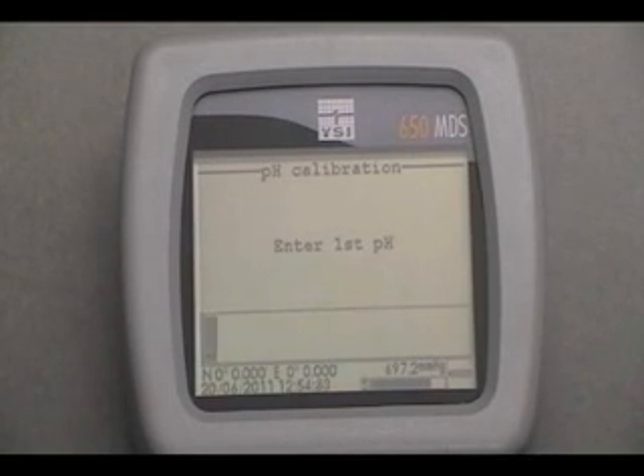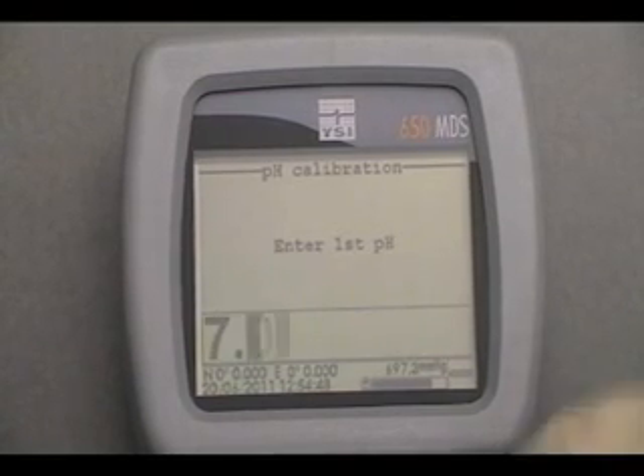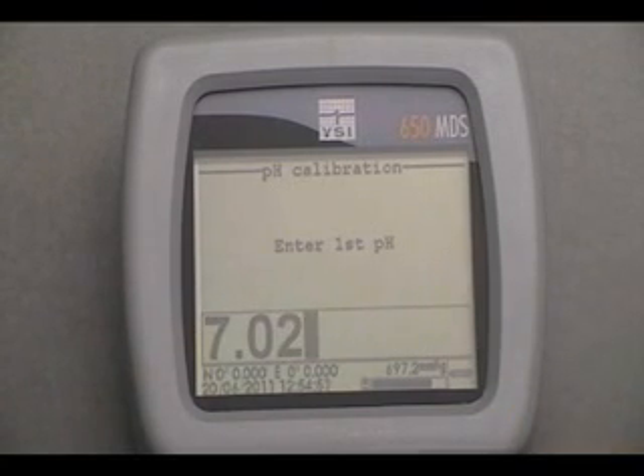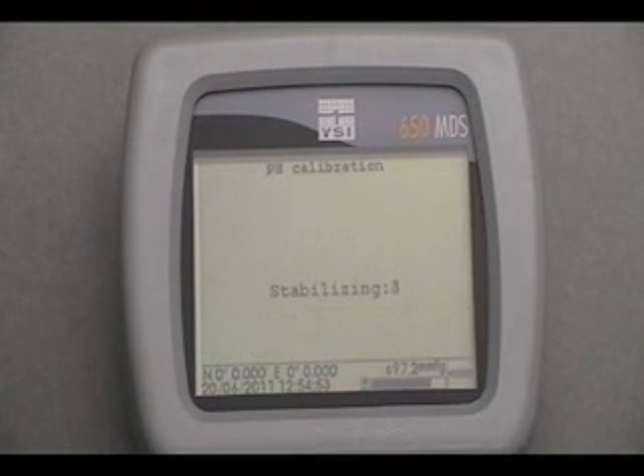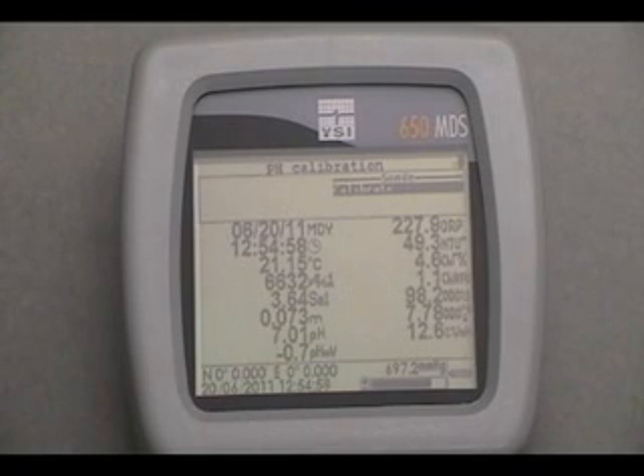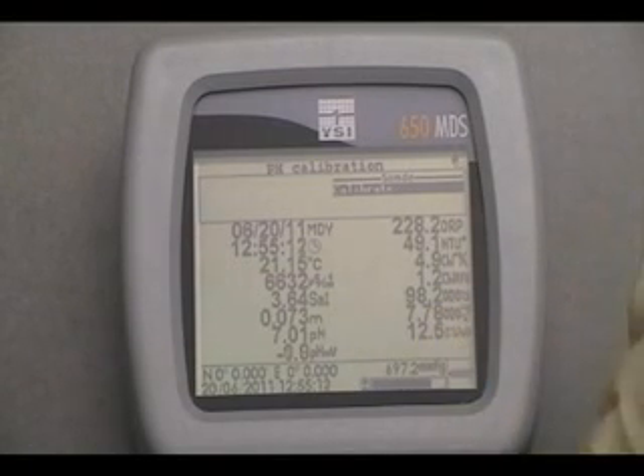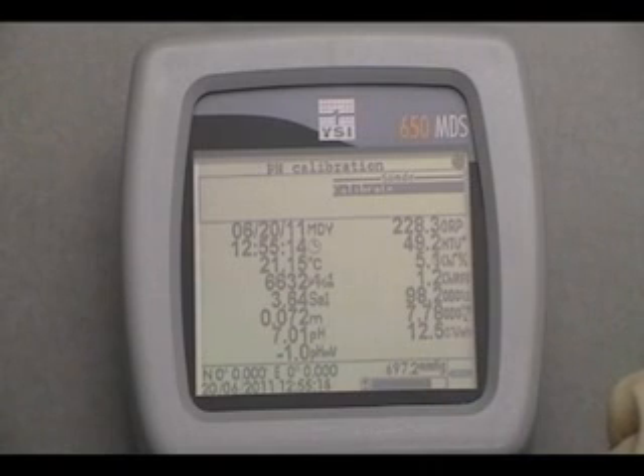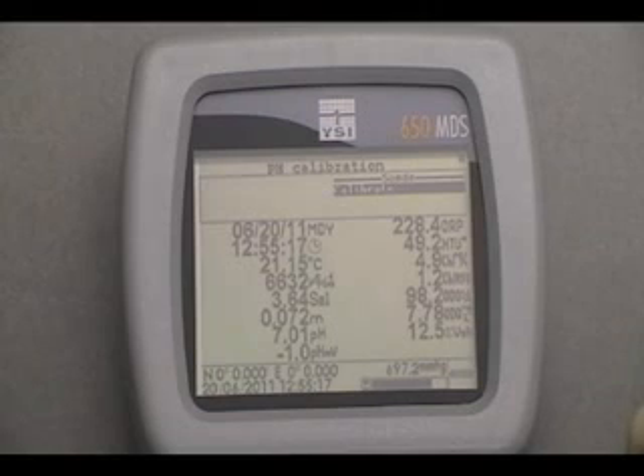In this case, we are calibrating at 20 degrees Celsius. The input value will therefore be 7.02. Press Enter. The values of all the sensors will appear on the screen and change as they stabilize. Step 8. Record the pre-calibration reading in pH units on the calibration sheet. Step 9. If the pH reading is not changing significantly, press Enter, and the calibration will be accepted.